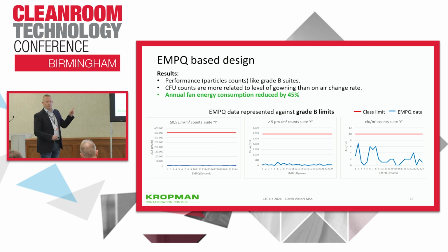And here I show you the results. EMPQ study again, but I represent it not against grade C limits but against grade B limits. And again, for the particles, a big gap between class limit and the measured concentrations in the worst case scenario. For CFUs it's different. We see a lot of peaks, but I think that's more related to the level of gowning and level of cleaning in the clean room than to the air change rate. And after 1 year of measurements, we saved almost 45% of the fan energy.